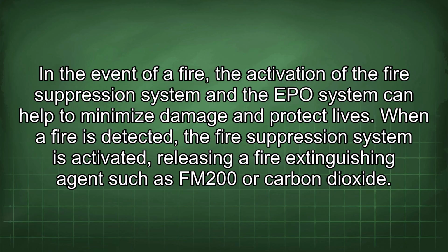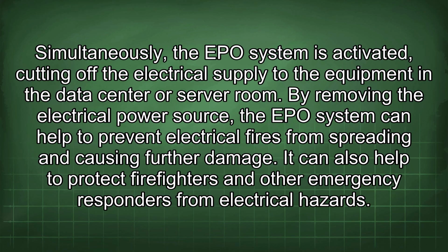When a fire is detected, the fire suppression system is activated, releasing fire extinguishing agents such as FM200 or carbon dioxide. Simultaneously, the EPO system is activated, cutting off the electrical supply to the equipment in the data center or server room. By removing the electrical power source, the EPO system can help to prevent electrical fires from spreading and causing further damage. It can also help to protect firefighters and other emergency responders from electrical hazards.